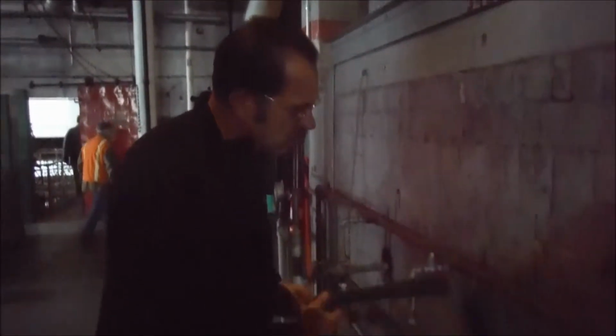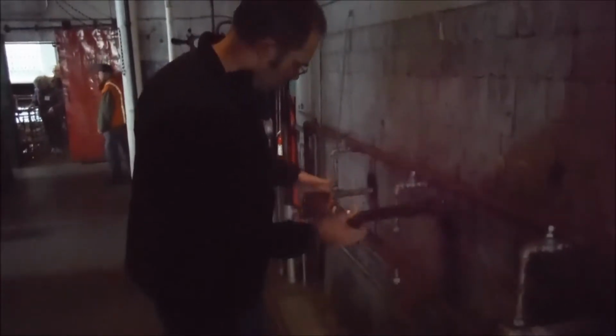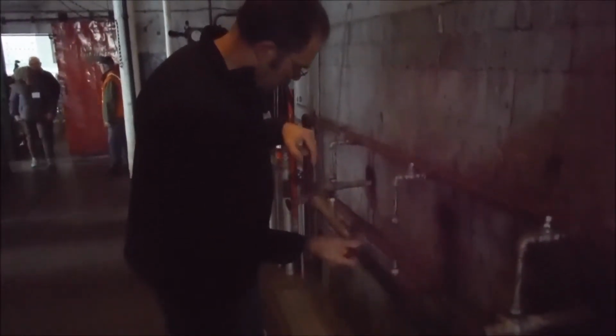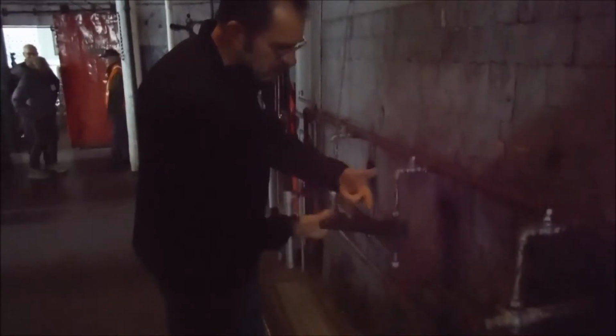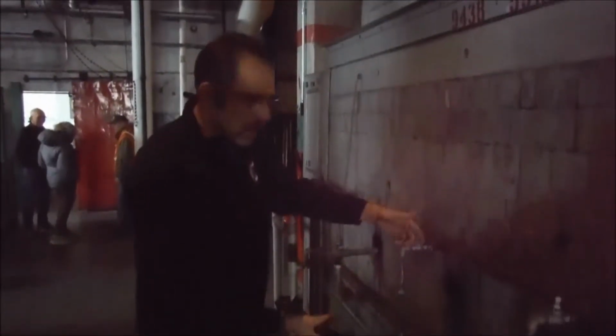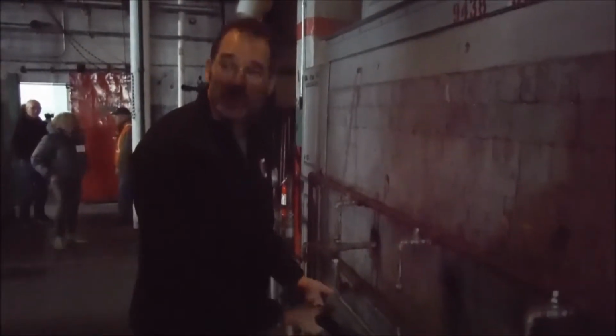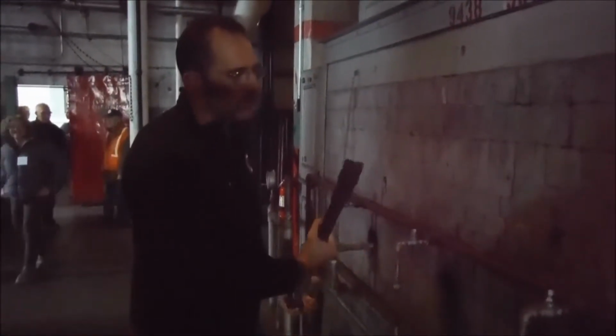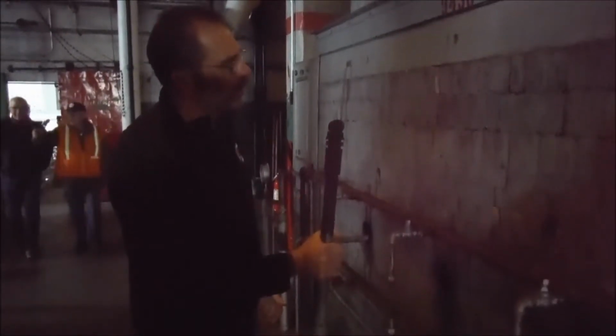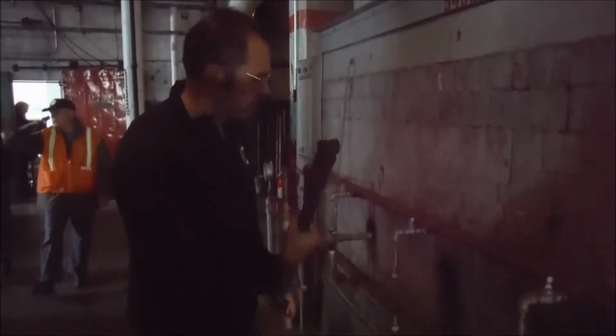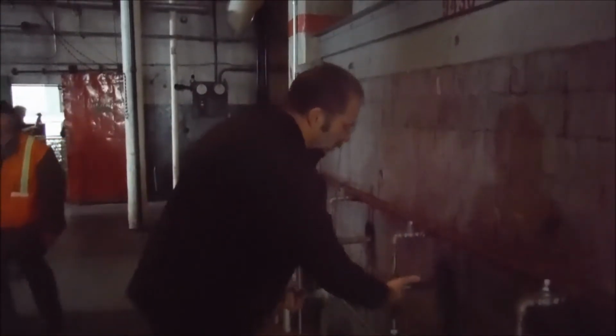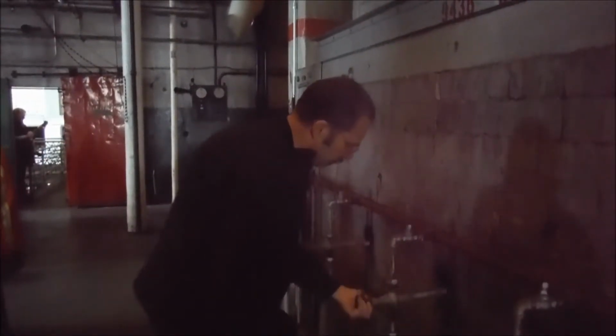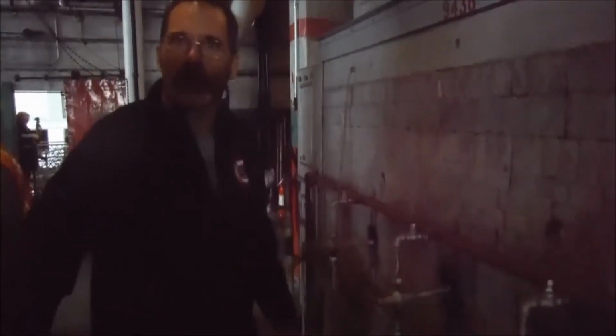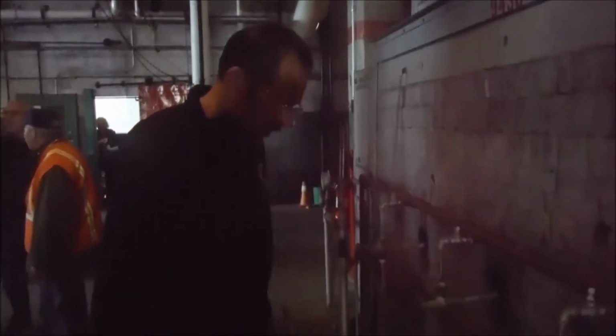Fuel oil pipe. A lot of times you have a supply and a return because you've got a constant flow. And this is a burner or an atomizer. Fuel would come in through here, spray out through here and just be burning like crazy in there, just a jet of raw fuel combusting in the boiler. One of the jobs we had to do in the Navy was, our sprayer tips were way different, but every 24 hours you had to change out the burners and clean the sprayer plates with a brass scraper and a brass brush so you wouldn't damage the holes.